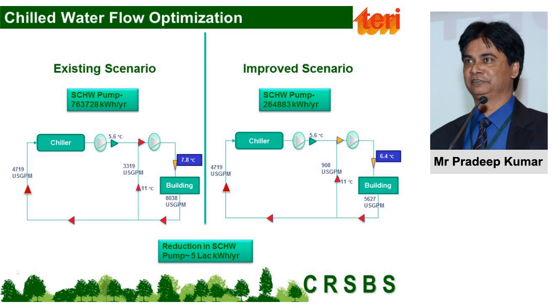The next, we also felt that because a controller was installed, but was not operating in the auto mode, it was operating in manual mode. So we called the vendor and asked, okay, bring it into the auto mode, install the pressure transducers and other things. Because there were 3 circuits, and generally your controllers record the worst one and set the flow rate based on that.